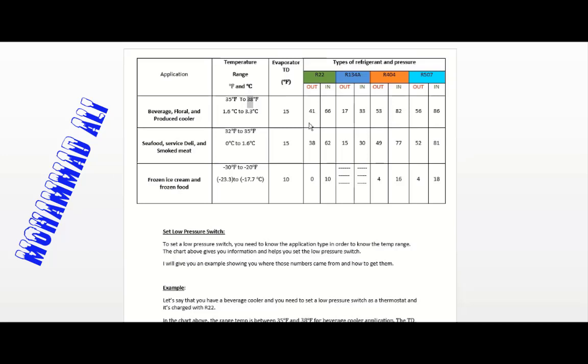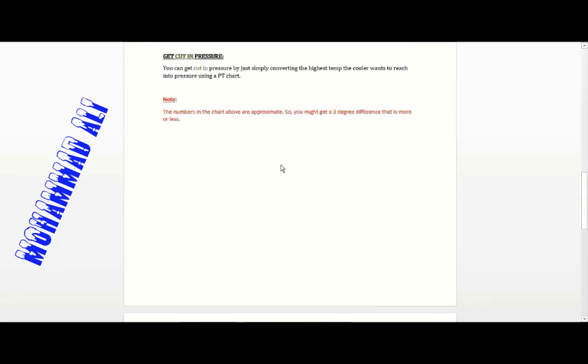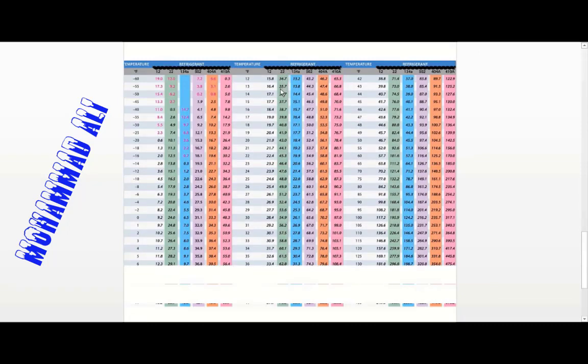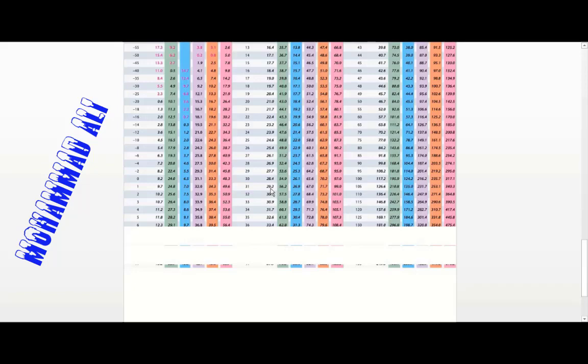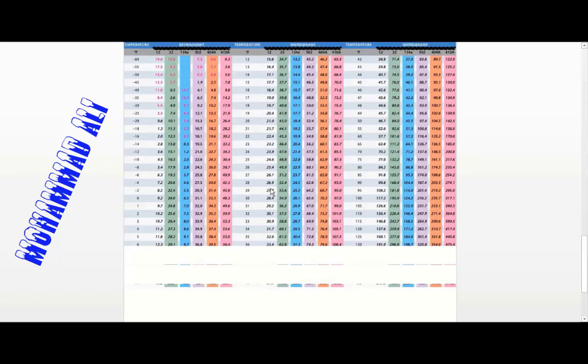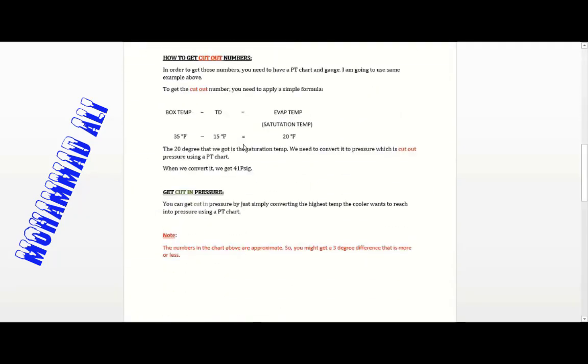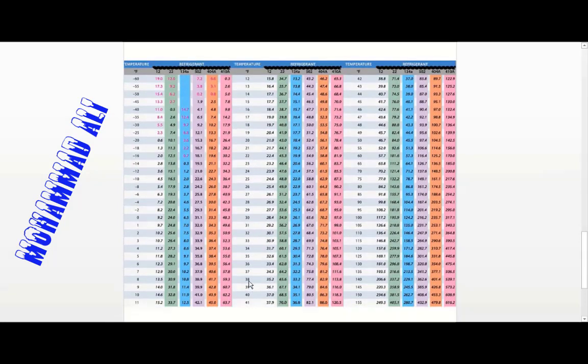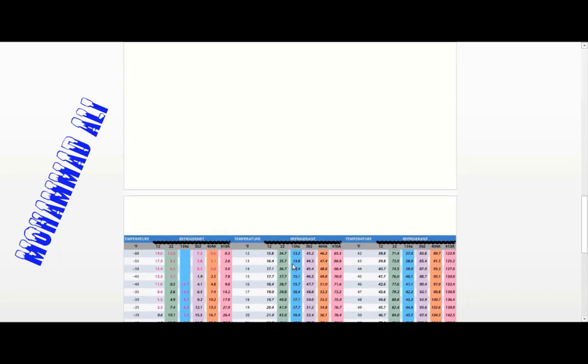Now to get the cut-in pressure, we simply convert the cut-in temperature of 38°F using the PT chart. Looking up 38°F for R22, we get 65.6 PSI, which is almost the same as the chart value of 66 PSI. So that confirms the cut-in pressure.